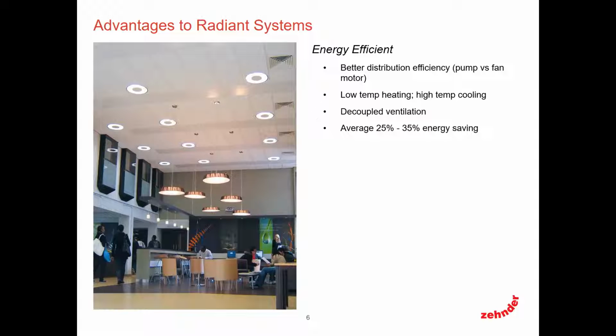When we're talking about water temperatures, we're talking about lower heating temperatures. Generally, I'm not looking for 180-degree hot water temperature to do your heating. Generally, I'm looking for something around 120 to 140. Same thing on the cooling side. Typically, in most systems, we're not looking for 42 or 45-degree water. Typically, I see somewhere between 55 to say 60 degrees.